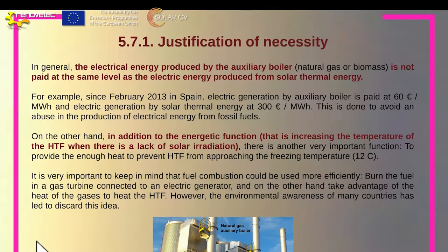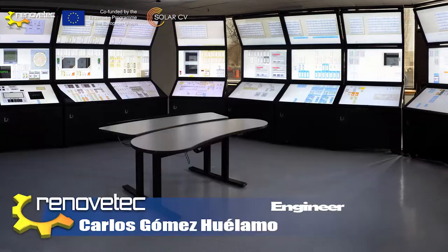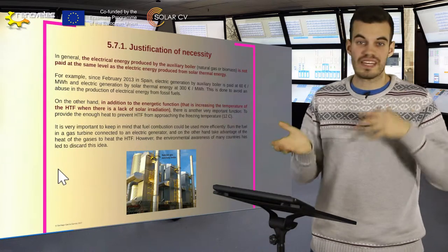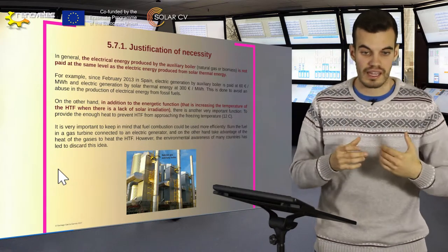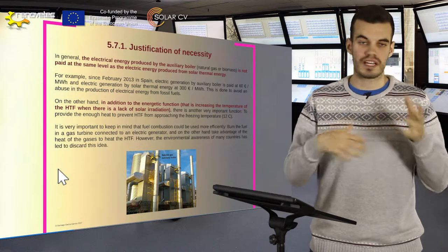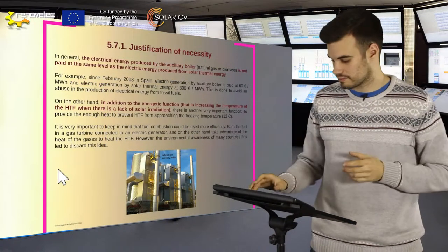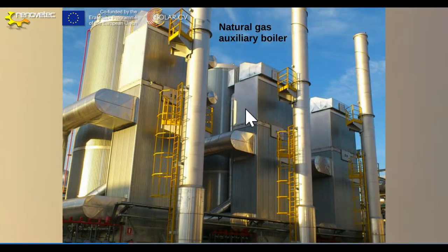On the other hand, in addition to this energetic function — that is, to increase the HTF temperature to let the plant operate under nominal conditions — you have the anti-freeze function, which is to provide enough heat to avoid the HTF reaching its freezing temperature. The HTF freezing temperature is more or less 12 degrees. If the temperature is equal to or below, or even close to this temperature, the pumps may break. Here you can see an example of three natural gas auxiliary boilers in vertical position.